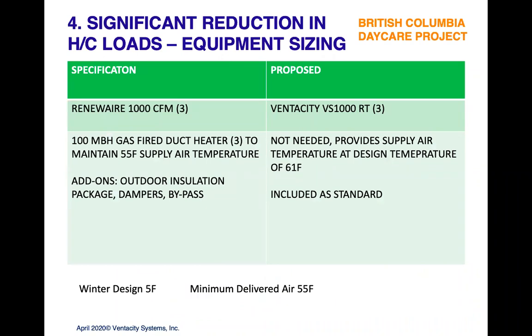This is a project in British Columbia we looked at. It's a daycare center. They had originally planned on 3 RenewAire, which are very conventional ERVs with conventional efficiency. The design temperature is 5 degrees Fahrenheit. The minimum delivered air temperature is 55 degrees. They do not want to be bringing colder air than that into the building. And to do that with conventional ERVs or HRVs, you're looking at requiring post heating. In this case, they needed to put in gas-fired duct heaters, 3 of those for those 3 ERVs.